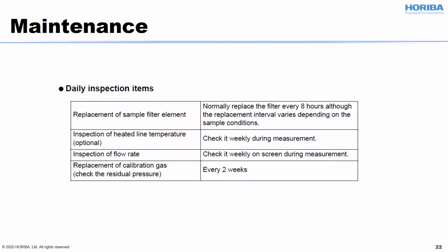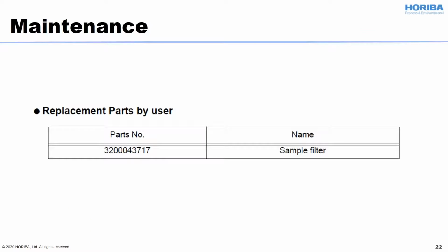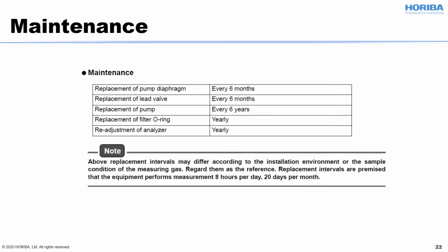This page is showing some maintenance information. I'm showing right now a daily inspection item. Basically, replacement of the sample filter element is the one you normally need to do. This is the sample filter, a consumable part. Replacement of the pump diaphragm and the lead valve needs to be done every 6 months, and the pump needs to be replaced every 6 years. Other than that, the O-ring and analyzer adjustment need to be done annually.